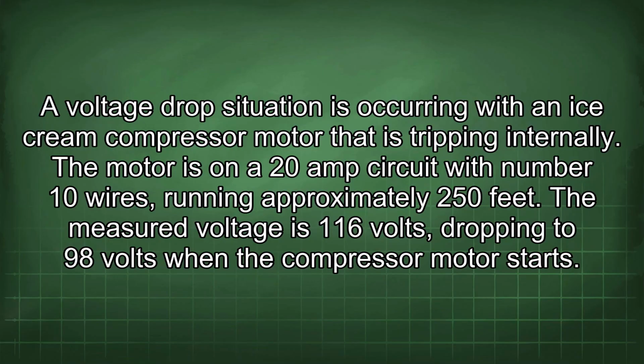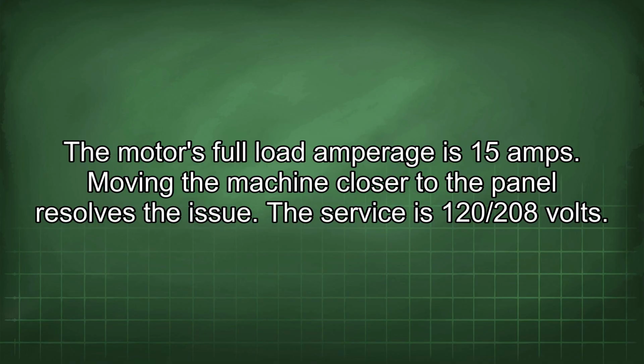A voltage drop situation is occurring with an ice cream compressor motor that is tripping internally. The motor is on a 20 amp circuit with number 10 wires, running approximately 250 feet. The measured voltage is 116 volts, dropping to 98 volts when the compressor motor starts. The motor's full load amperage is 15 amps. Moving the machine closer to the panel resolves the issue.